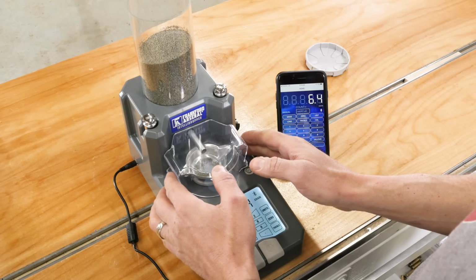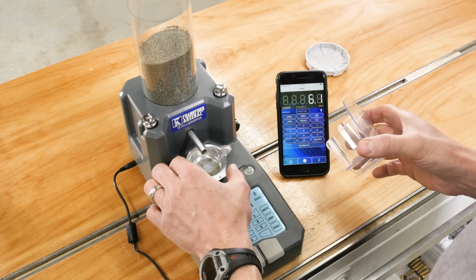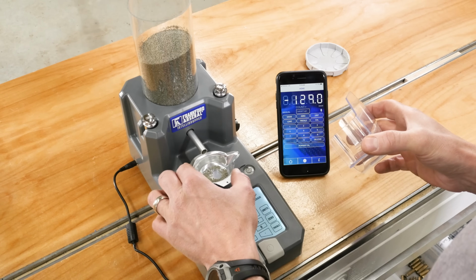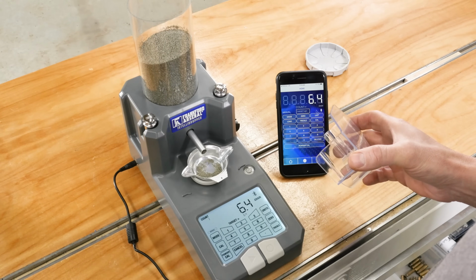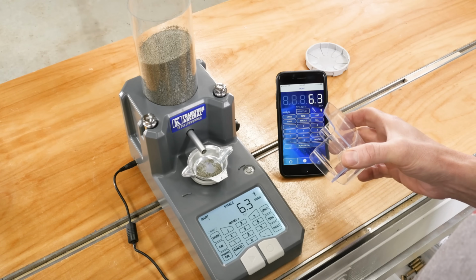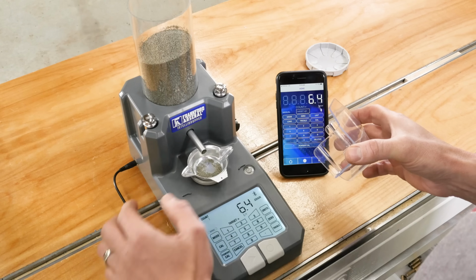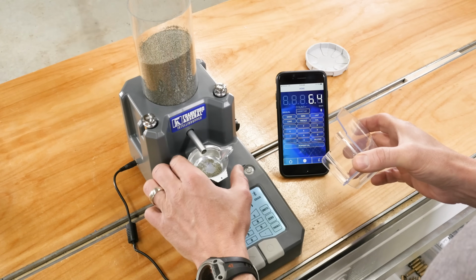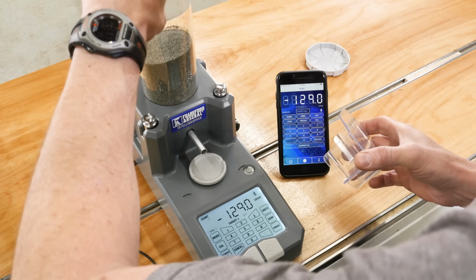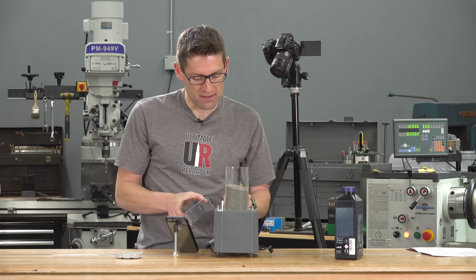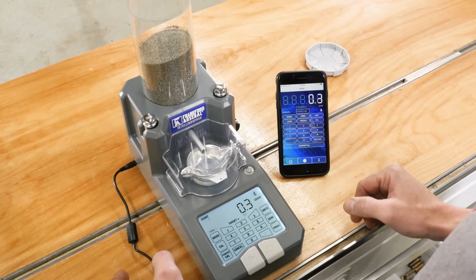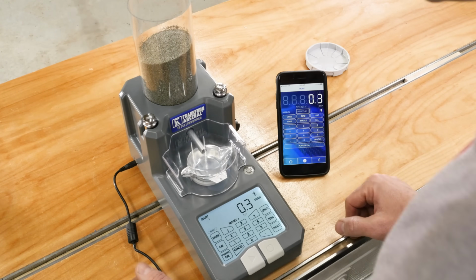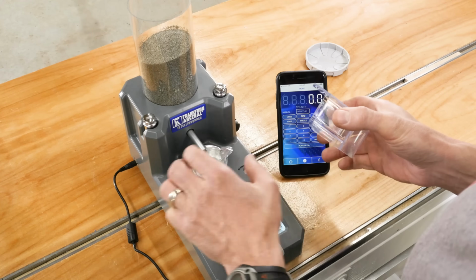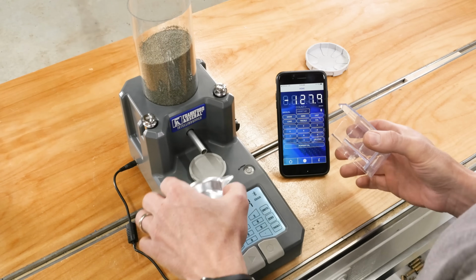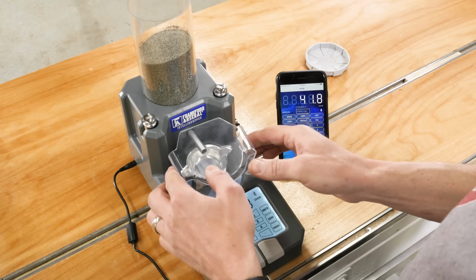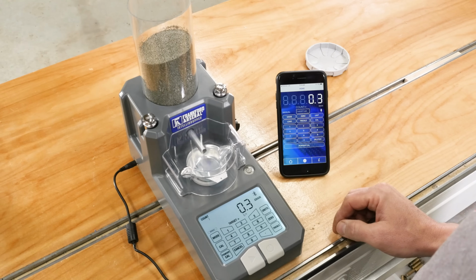Okay, so we've got stable. Let's take this guard off. We'll do the test where we remove the pan and we put the pan back. Okay, we're within 1/10 of a grain there. Oh, 6.4, there we go. We just have to give it a little bit of time to stabilize. Okay, so let's dump that. Go ahead and dispense a new load. Make sure I have no powder granules here. It looks pretty clean.